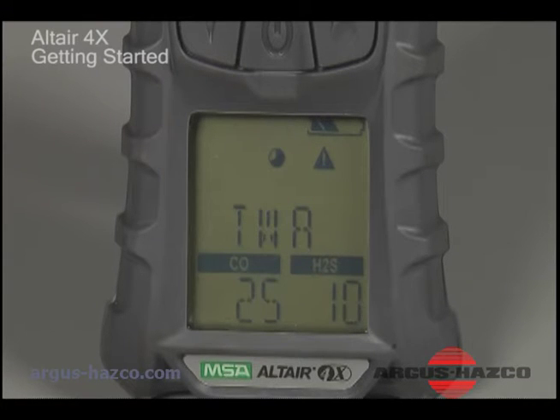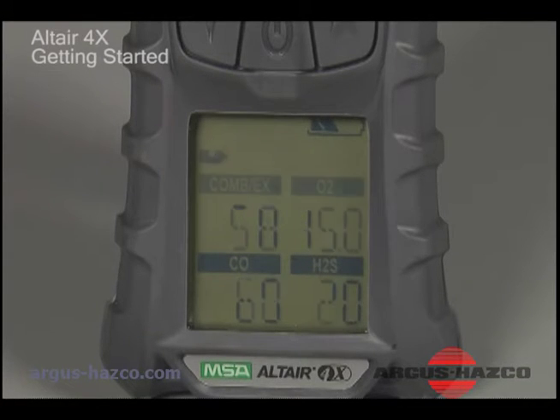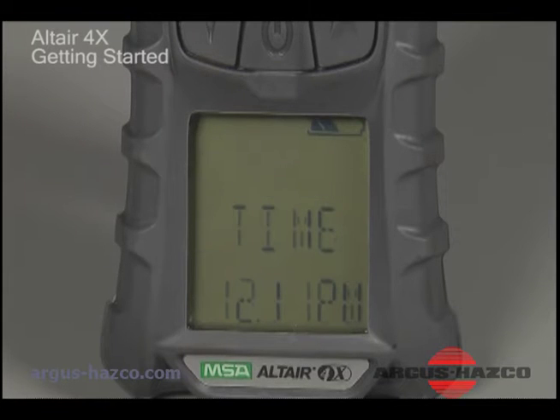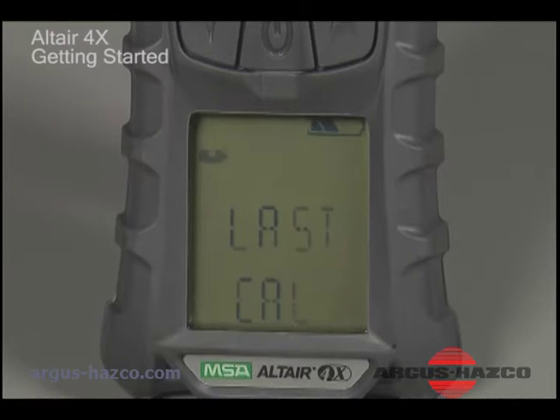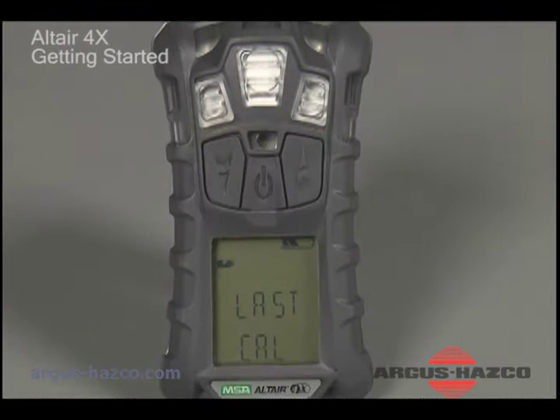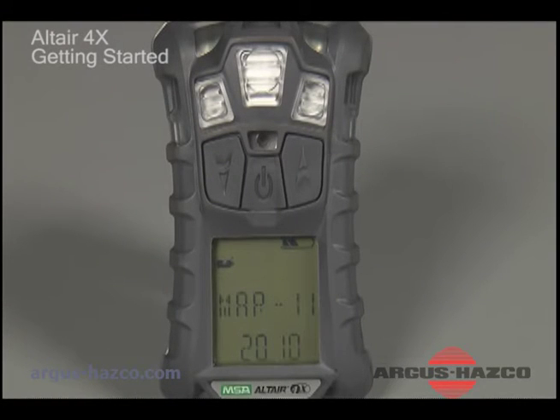The startup sequence also displays calibration gas settings and time and date, indicates the last calibration date if the feature is activated, and indicates the calibration due date if the feature is activated.